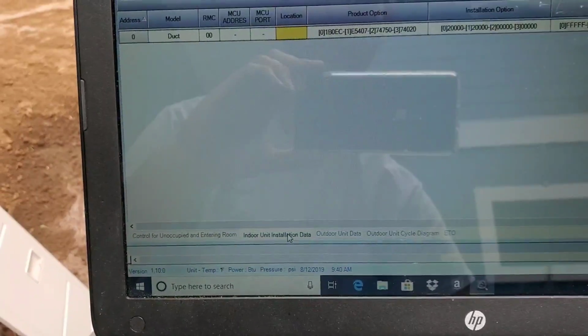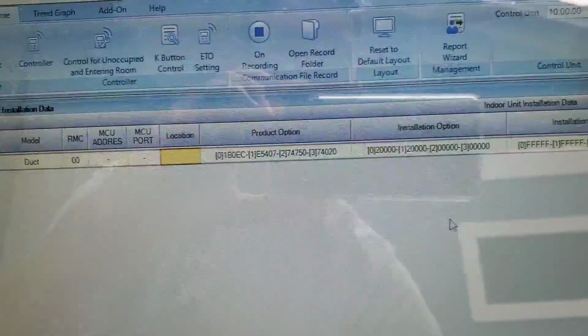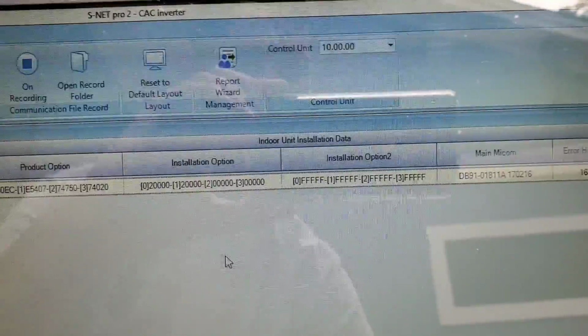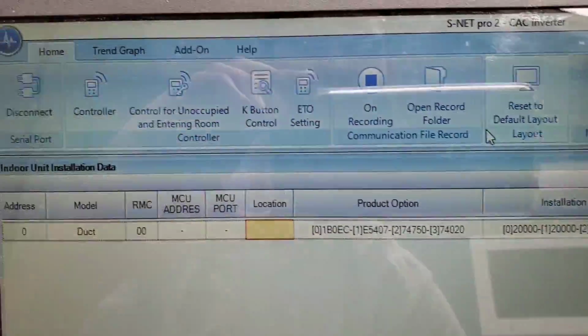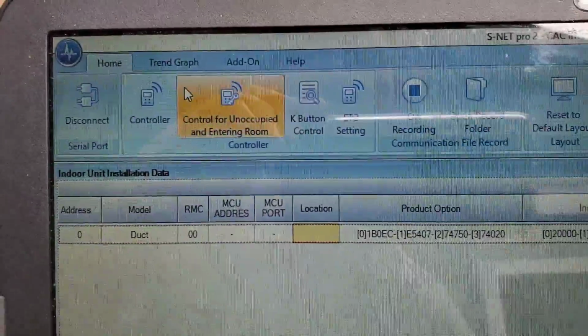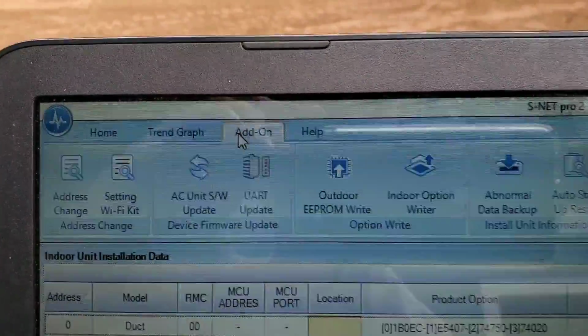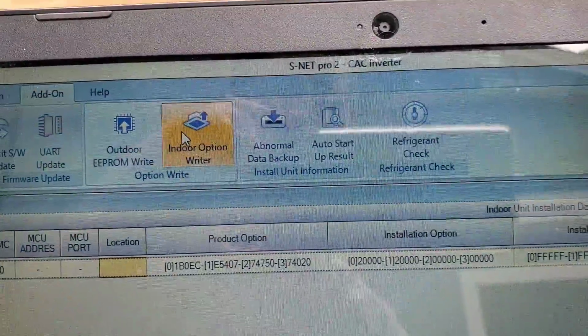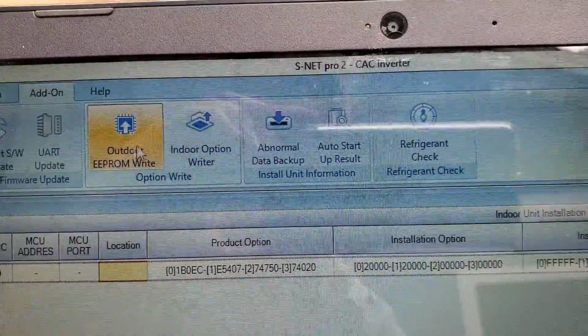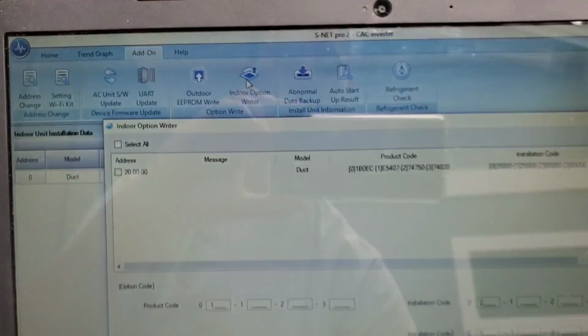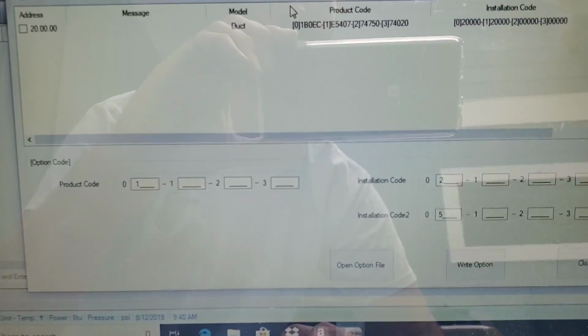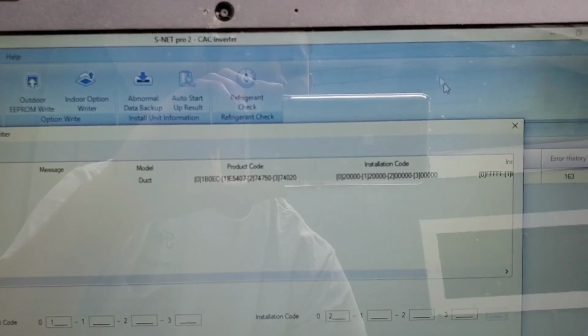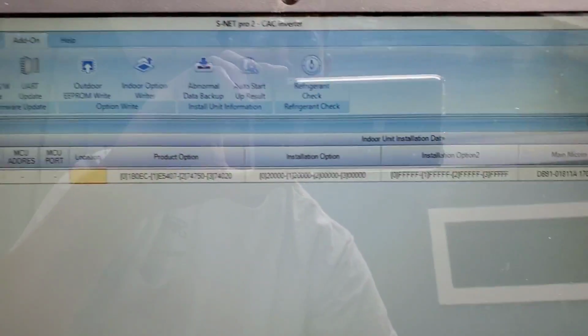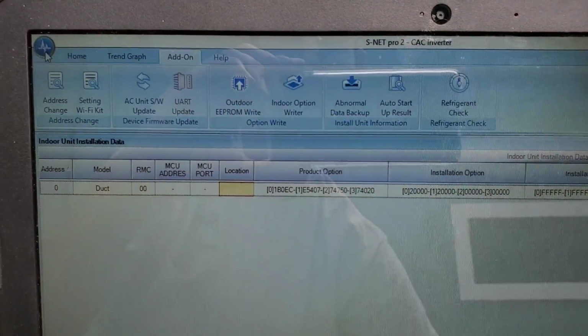Now I'm going to go to indoor unit installation data. See, there's my product options, my installation options, and I can change those by going up here to add-on. See where add-on is? Hit add-on, indoor option writer, okay. Outdoor EEPROM write, or I can go to indoor option writer and type in a new product code. Those installation product codes are found in your service manuals, or actually your installation manuals that come with the equipment will have that as well.